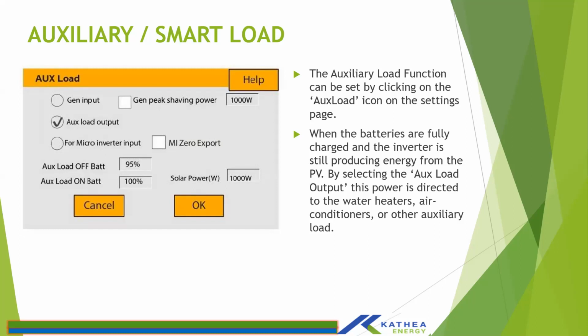Rather than throwing away the surplus power, you can actually use the auxiliary port. Since the system is off-grid, it doesn't have the function for non-essential loads, right? So it can only supply loads connected on its backup, and we still have excess power. You can use this port as a smart load port. Then you can connect your high power loads, for instance your pump, and the system can power up those loads at a percentage which can be programmable.